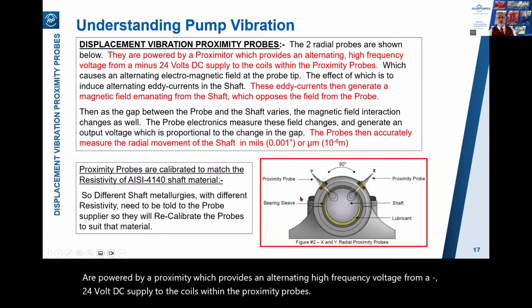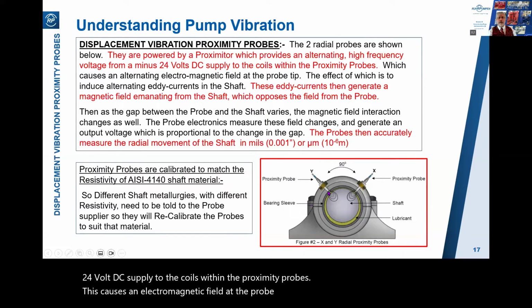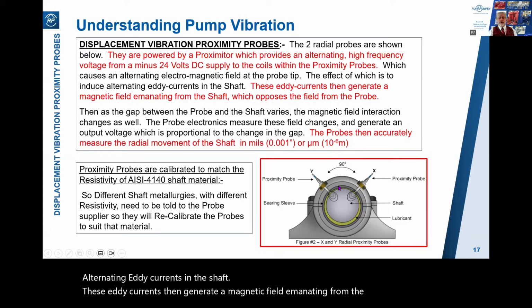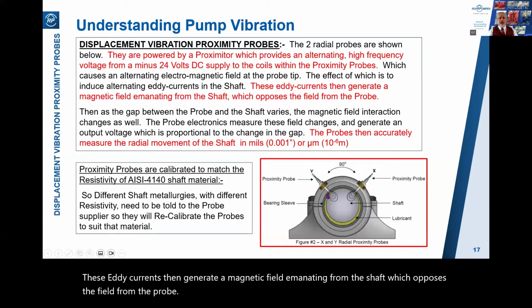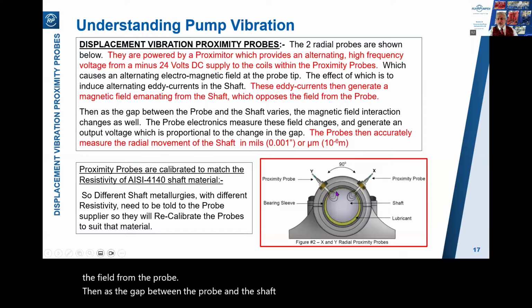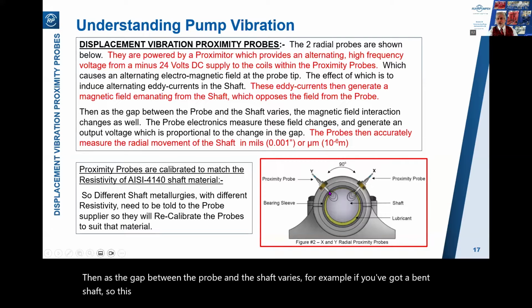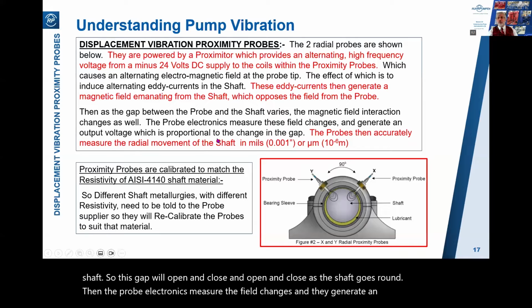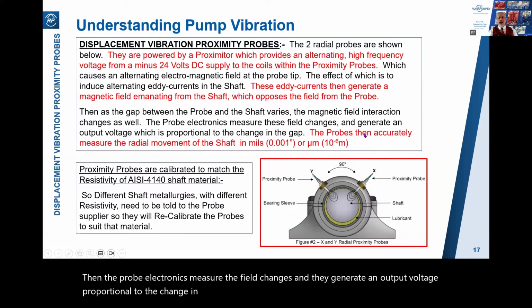This causes an electromagnetic field at the probe tip here, the effect of which is to induce alternating eddy currents in the shaft. These eddy currents then generate a magnetic field emanating from the shaft, which opposes the field from the probe. Then as the gap between the probe and the shaft varies, for example, if you've got a bent shaft, so this gap will open and close as the shaft goes round, then the probe electronics measure the field changes and they generate an output voltage proportional to the change in the gap. So they accurately measure the radial movement of the shaft in mils or in microns.